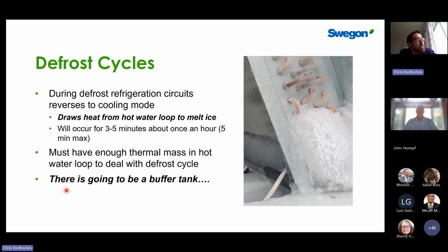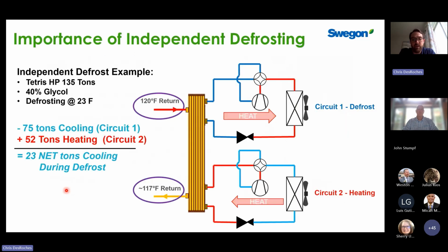So because the coil temperature gets very cold, the worst case that we're actually going to see for defrost is really when we're between 35 and 40 Fahrenheit ambient temperature. Because at those ambient temperatures, we can still carry a lot of moisture in the air, but the surface temperature is below freezing. So we're going to have that moisture freezing to the coil, so we need to get rid of it. So typically we'll do this with air source heat pumps with what we would call a reverse cycle defrost, which is a fancy way to say we're putting the unit into cooling mode for a couple minutes.